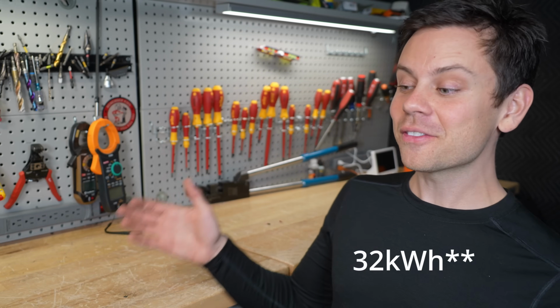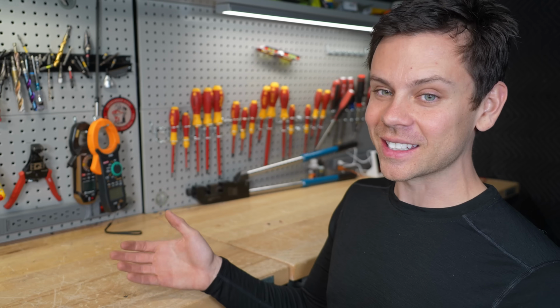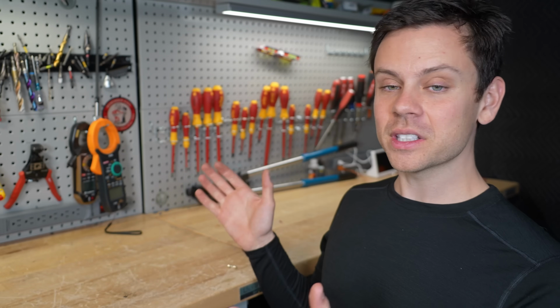Next, for this capacity of battery, I think the BMS should be larger. A 200 amp BMS on a 34 kilowatt hour battery is crazy. For the same capacity with server rack batteries, you would have 600 amps of output. So keep this in mind when you're designing your system.